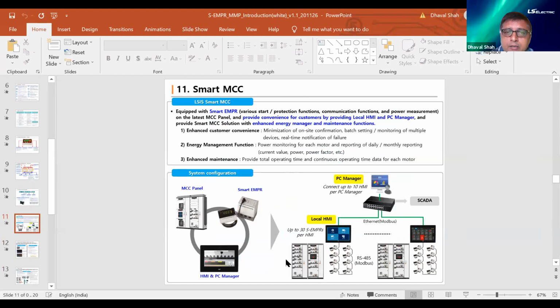So moving ahead with intelligent MCC or smart MCC, we can go ahead for this enhanced customer service with minimization of on-site confirmation. But basically here in a nutshell, what we would say is that you can configure for n number of relays if you have the software, and that software can be communicated. Means 30 EMPR can be connected to one HMI, and such HMIs can be connected to SCADA through Modbus TCP.